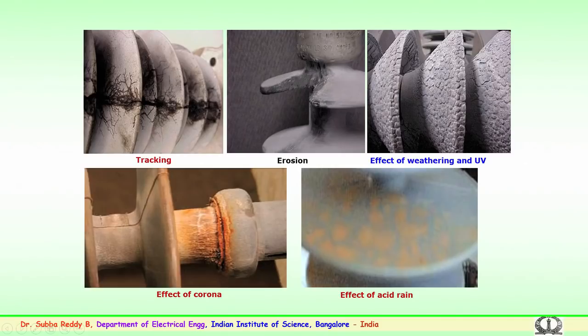This shows the effect of corona over a period of time. You can see the metallic junction to the fiberglass rod. This is a very critical area which has to be taken care of. Once there are microstructure damages as mentioned, water, moisture or mist and fog seeping in could lead to brittle fracture. Corrosion happening near the metal end fittings is not a healthy thing, so it has to be properly ensured that the coatings of the metallic end fittings are done and they are properly protected. Similarly, as discussed, the effect of acid rain: acidic components spread from factories near the transmission system could again lead to surface degradation over a period, and this could damage the insulator in the field.